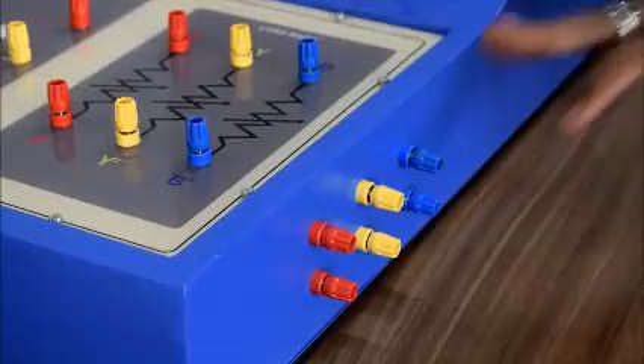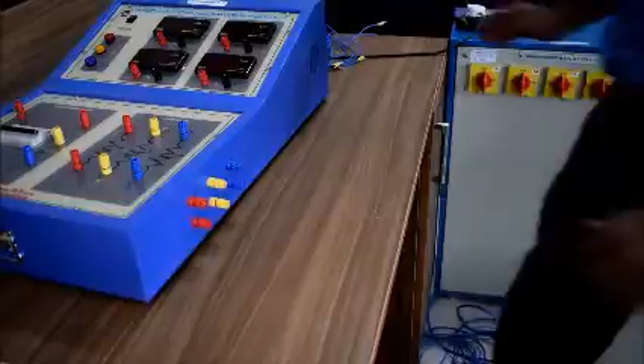Here I'd like to give a suggestion: instead of connecting all at the same terminals, on the kit he has provided terminals on the side as well. Internally, the upper R, Y, B is shorted with this upper R, Y, B, and the lower R, Y, B is shorted with the lower R, Y, B. So connect the terminals coming from the load to the upper terminal of this R, Y, B on the load bank, and similarly connect the lower terminals of R, Y, B to the lower terminals of the load bank.